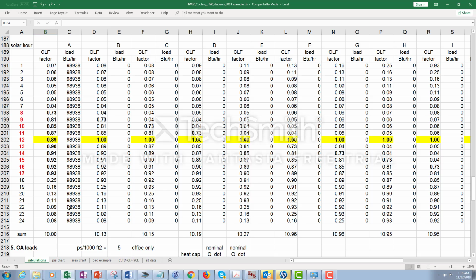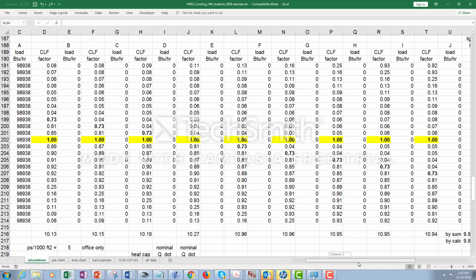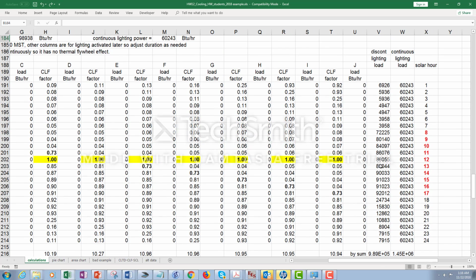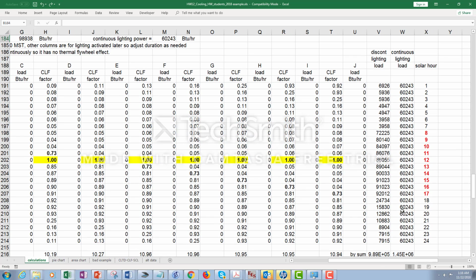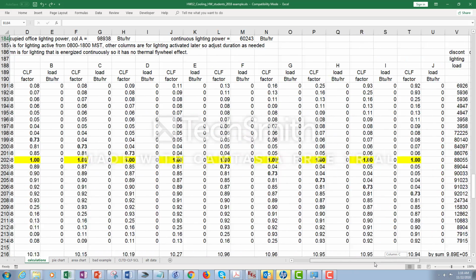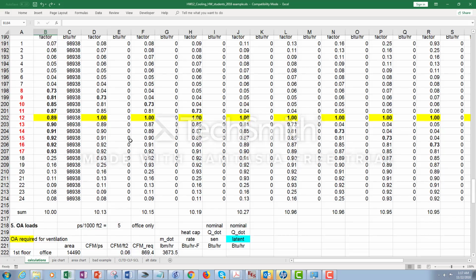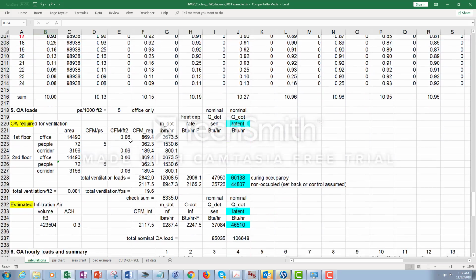we take the hourly load and multiply it by the appropriate cooling load factor, which is exactly the same one for people. Now for the security lighting, I just put this in here primarily because there probably would be some, but that's running continuously. So it's already saturated the heat capacity of the building for this energy input. So it's going to be continuous for the whole period. Okay, so that's given us our people and equipment and lighting.